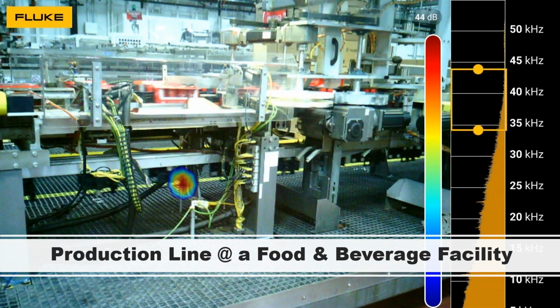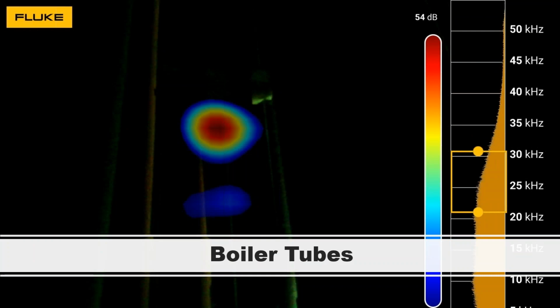You name it. It doesn't matter. Plenty of stuff going on in this production facility. A lot of canned beverages going by, and so there's a lot of noise, there's a lot of hissing, there's a lot of rumbling. We're still able to pick up the air leak underneath the table. And you don't have to be right up on it either.